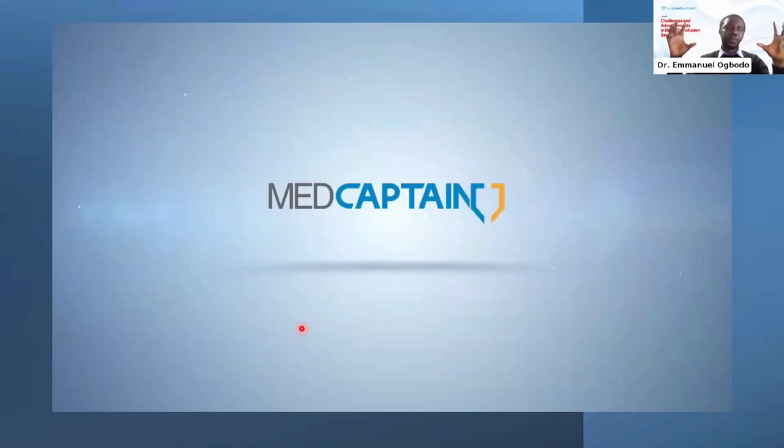So how does this automation work? Of course, there's going to be reagent inside the analyzer first. So what should be in that reagent? Now, remember that when you are doing your blood group, you are using Antisera, like it's being used in Nigeria. You use Antisera and then test the patient's blood group. But now you have a card that already has this Antisera embedded in it, whether it is Antisera A, Antisera B, or D. Of course, there's also a negative control where there shouldn't be anything, to show us whether the result is valid or not.